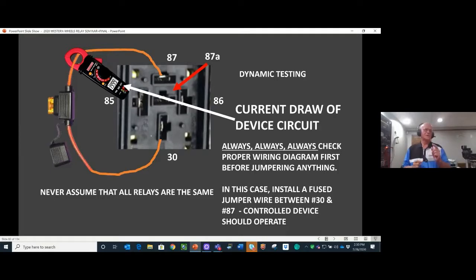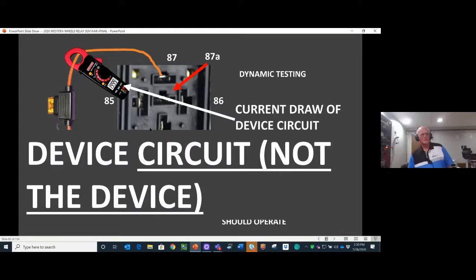Again, if the current is greater at the device than it was at the relay socket, something is reducing that current, and it could be in the positive side or it could be in the ground side. And of course, you can use voltage drop testing and circuit loading to find which one. Again, device circuit, not the device. Demonstration.